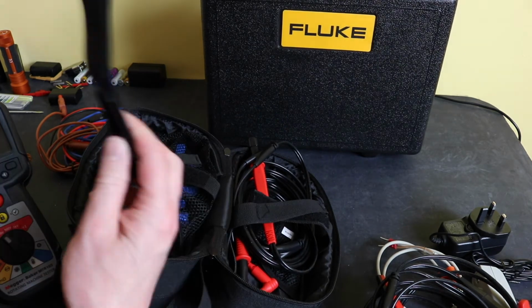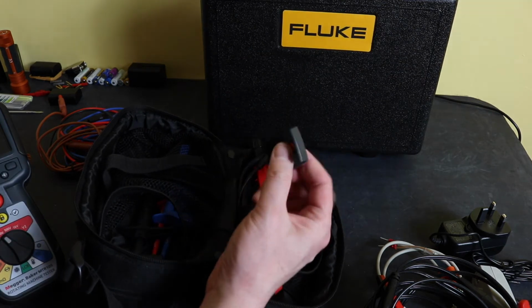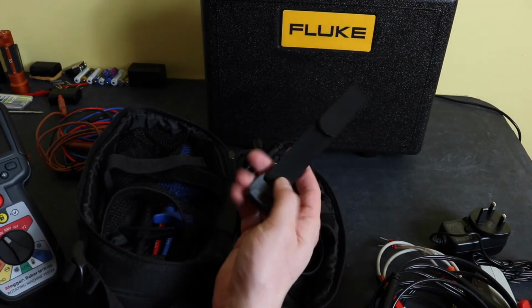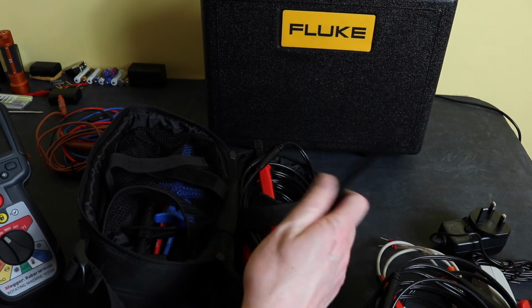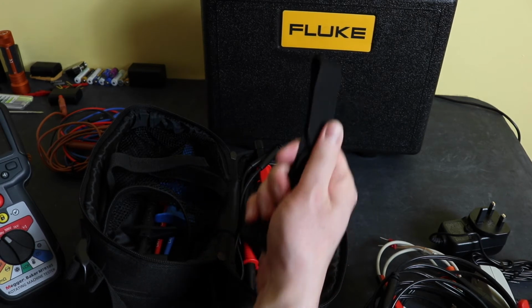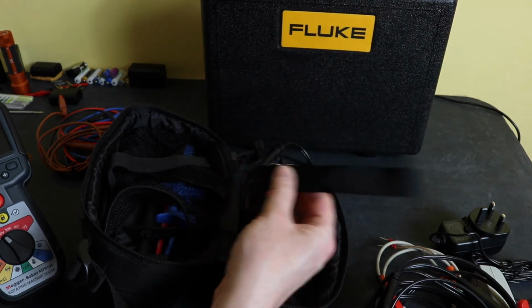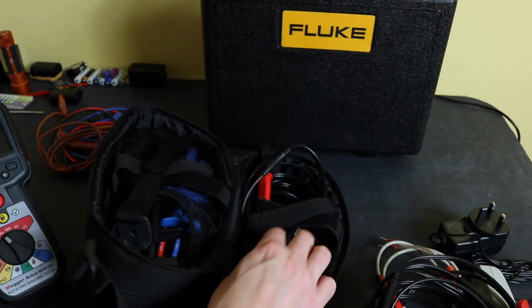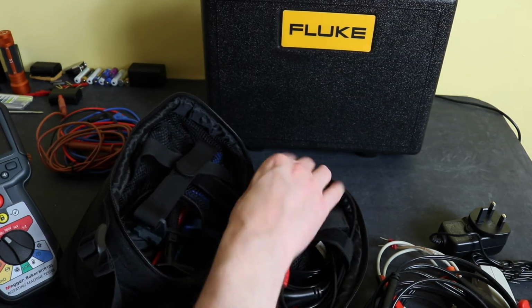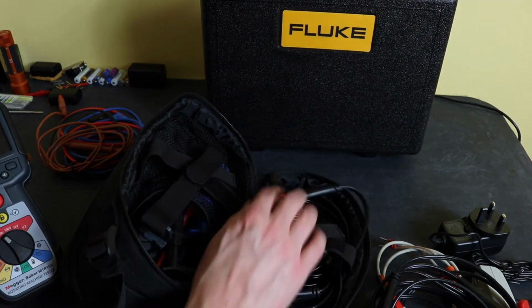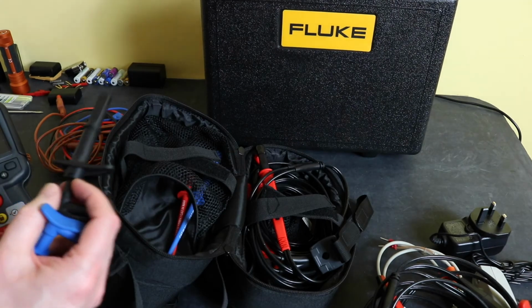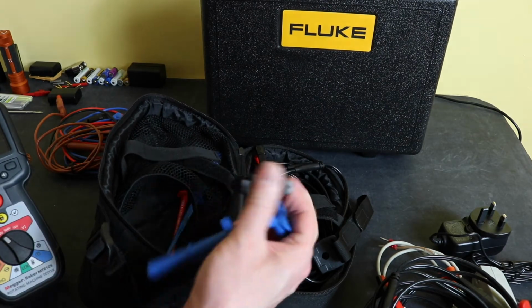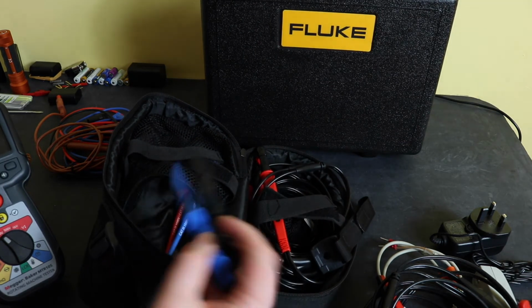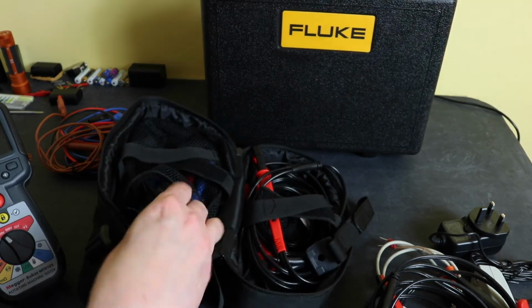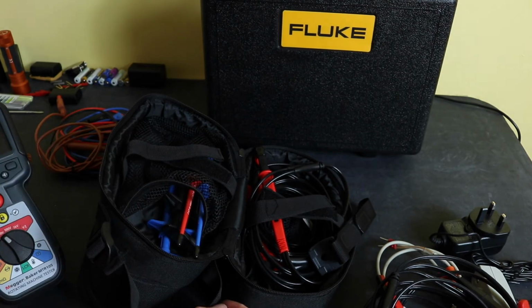What you do get with the Megger that you don't get with the Fluke is a hanging strap. This is non-magnetic, it's just a Velcro strap to hang around a pipe or something like that, and clips into the back of the instrument. These probes, the duplex probes, they're an extra that you can buy. Obviously with the Megger having a guard terminal, you get three crocodile clips or grippers, three probes and three leads.